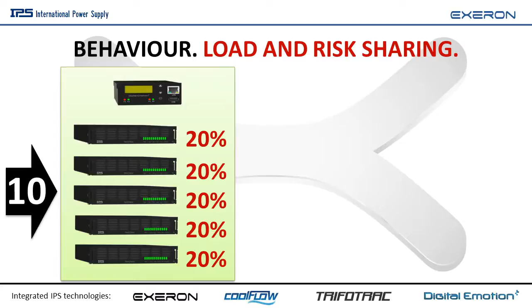Let me take a look at one of these situations. We at IPS are always thinking and prepared for even the worst case. Imagine a working system with 5 modules, for example grid charge controllers. Let me put at the input 10 units of power. Then what happens is balanced load sharing between the modules, each loaded with equal amount of power, let's say 20% each.